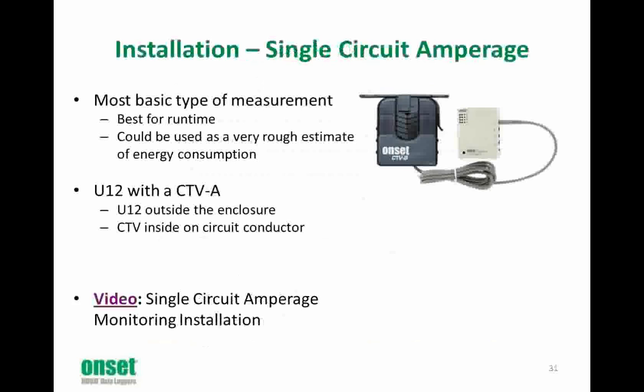Current metering is the most basic type of measurement. It is best for runtime and can be used as a rough estimate of energy consumption. For this, we'll use a U12 data logger with a CTV-A. It is always best to locate the CTV inside the enclosure and the data logger on the outside. This will ensure safe launching and reading out of the logger. We will now watch a short video of an installation.